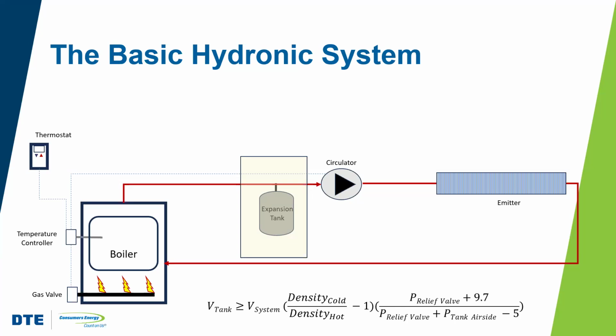Because it would be a smaller volume in there, and that's not what we want. So we want to make sure that we do properly size those expansion tanks. And just a quick note about expansion tanks. Very often the tank is marked with an acceptance volume. This is not the calculated minimum tank volume, right? This acceptance volume is the volume that the tank will accept for a given change in pressure. The calculated minimum volume of the tank is the size the tank needs to be for the system, right?